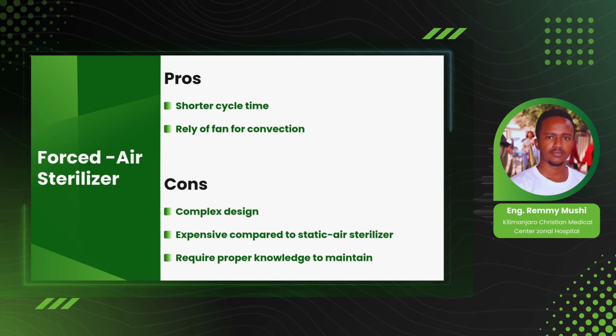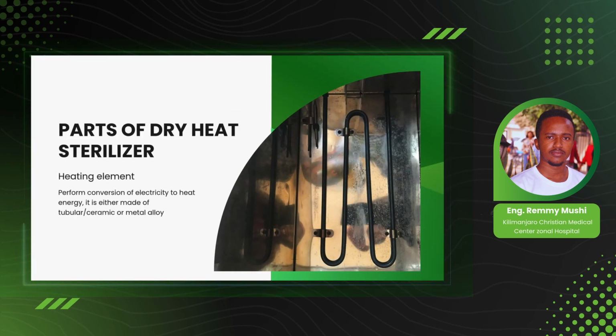With that in hand, we can now discuss the parts of the dry heat sterilizer. We are going to discuss all of them, the ones found in the static air sterilizer as well as in the forced air sterilizer. The first part is the heating element. A heating element is used to convert electrical energy into heat energy by dissipation. In most cases, the heating element is tubular, ceramic or metal alloy, depending on the volume of the chamber.